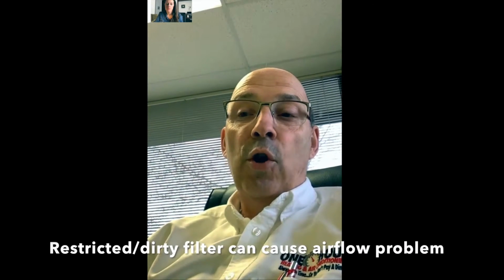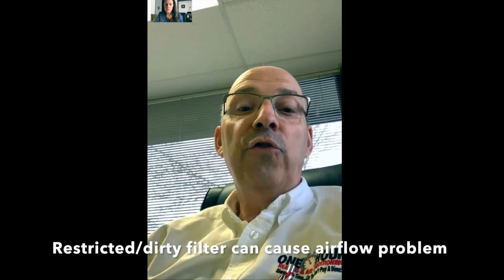Now, you can have an air conditioner that is properly charged but operating with a really restricted filter of some kind. That lack of airflow across the evaporator coil can also make it operate too cold and freeze the moisture on it, turning into a block of ice. So a super caked up filter can cause the same effect.